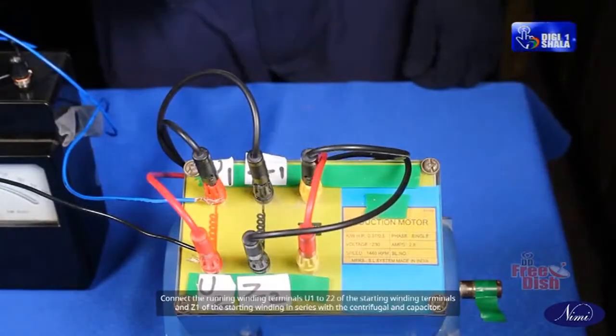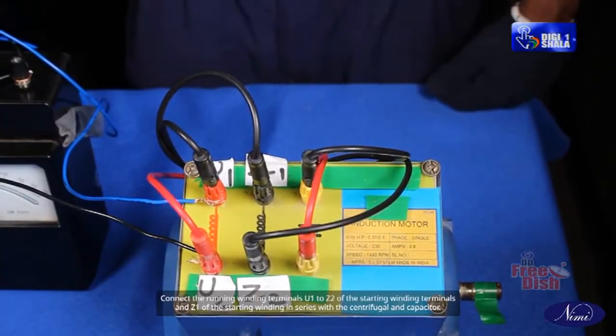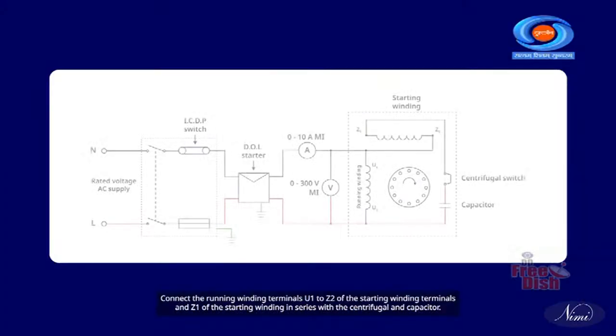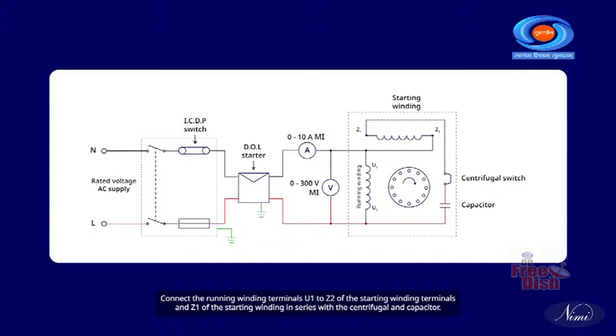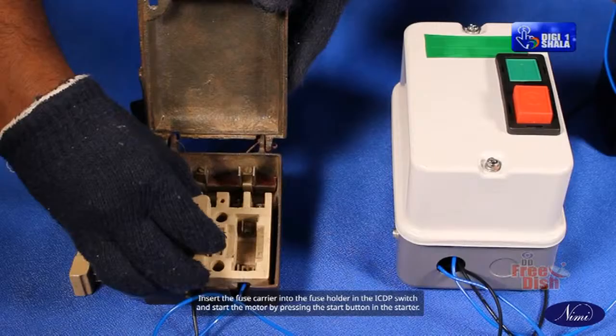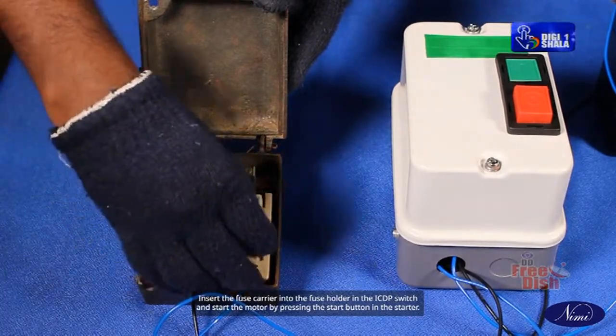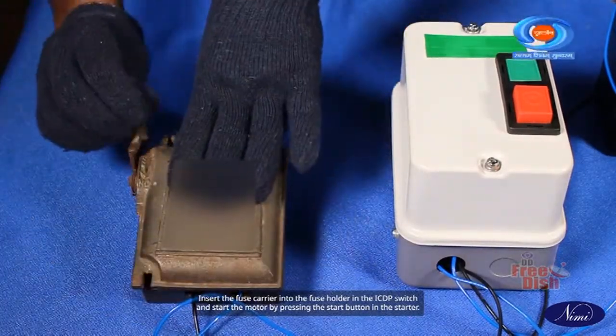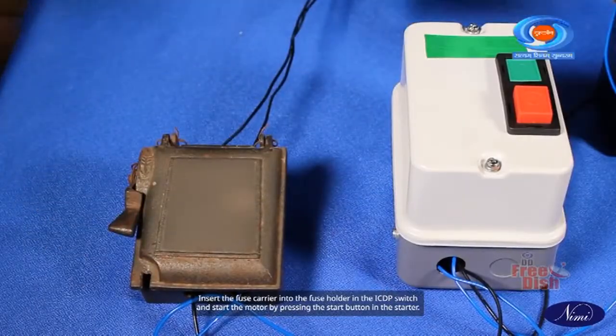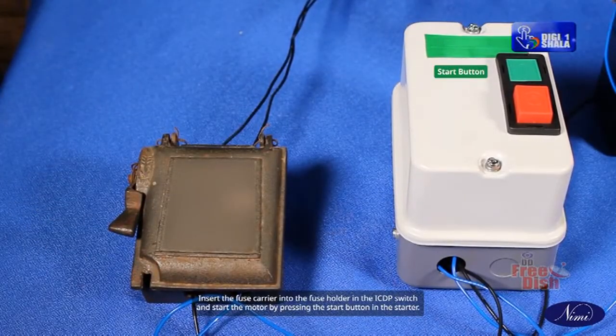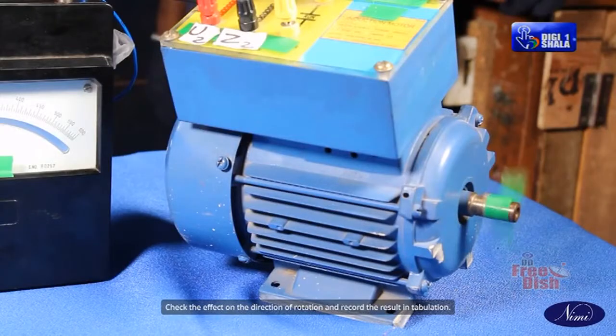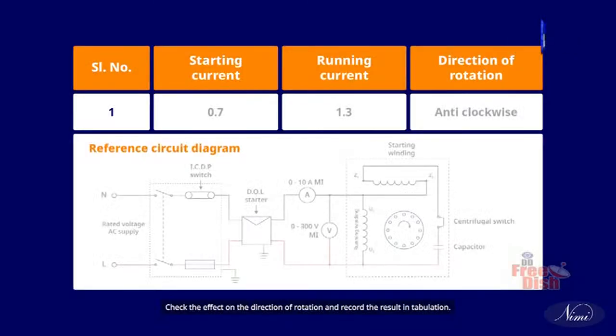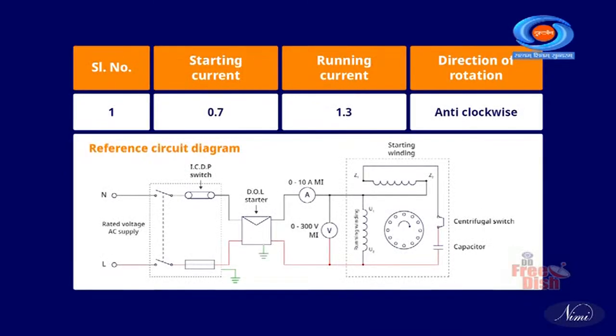Connect the running winding terminal U1 to Z2 of the starting winding, and Z1 of the starting winding in series with the centrifugal switch and capacitor. Insert the fuse carrier into the fuse holder in the ICDP switch and start the motor by pressing the start button in the starter. Check the effect on the direction of rotation and record the result in tabulation.